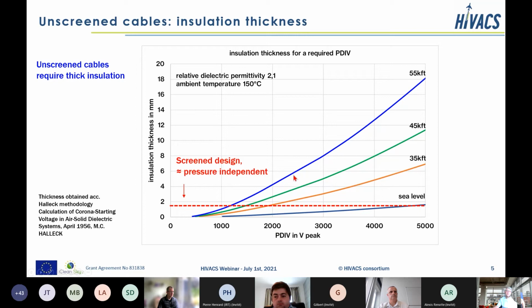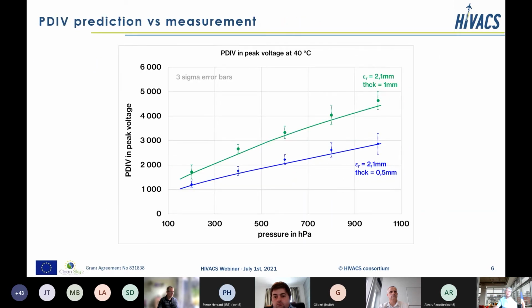The estimation of the partial discharge inception voltage is based on the Halleck method, which in principle is for uniform fields, but we also compared the prediction with measurements on cable samples. So the blue line is the partial discharge inception voltage as a function of the pressure for an insulation thickness of 0.5 millimeter, and the green line for a thickness of 1 millimeter. And the dots are the measurements we did, showing also the 3 sigma error bars. So from that graph, we can say that the method we have used to predict is in good concordance with measurements.